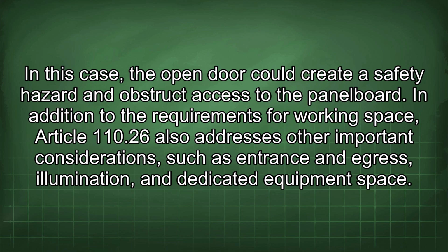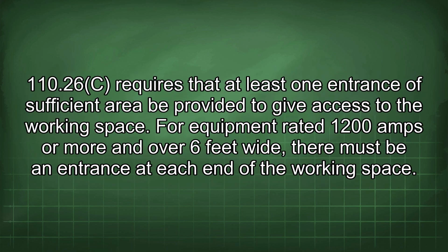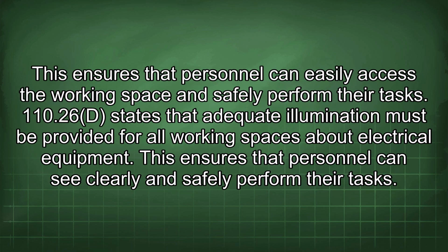In addition to the requirements for working space, Article 110.26 also addresses other important considerations such as entrance and egress, illumination, and dedicated equipment space. 110.26c requires that at least one entrance of sufficient area be provided to give access to the working space. For equipment rated 1200 amps or more and over 6 feet wide, there must be an entrance at each end of the working space. This ensures that personnel can easily access the working space and safely perform their tasks.